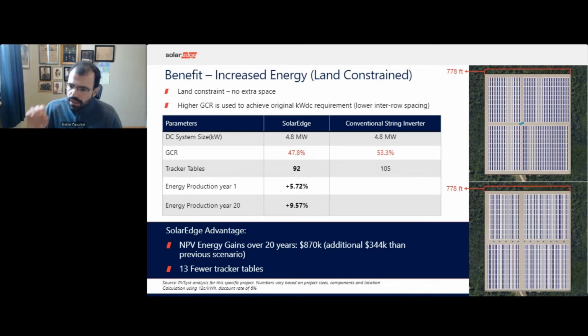And the bottom line is that the SolarEdge advantage remains: it needs 13 fewer tracker tables than the system with conventional string inverters, and has increased energy production. The energy revenue increase in this case is about $870,000, as an NPV over 20 years, which includes an additional $344,000 when compared to the previous scenario.